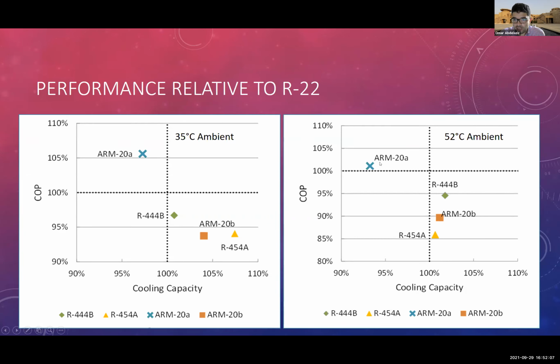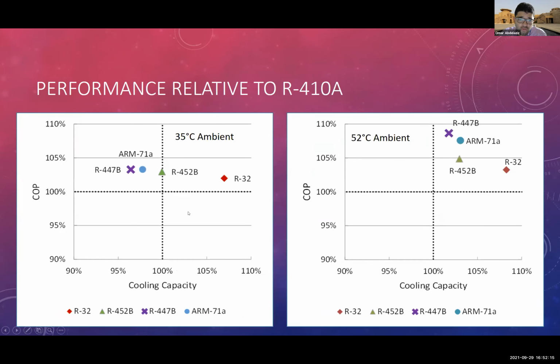Again, Arkema, you can also match it. You have lower capacity and slightly higher COP. For R410A application, we can see that most refrigerants have better COP, and some have exactly the same capacity. Some have slightly larger capacity at 35 degrees ambient, and at 52 degrees ambient, all of the refrigerants have better capacity and better COP.